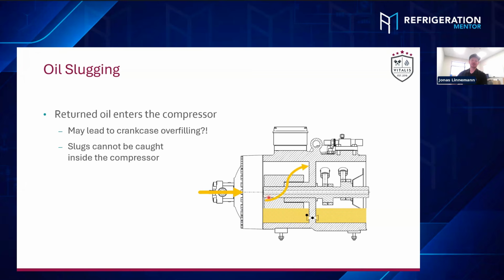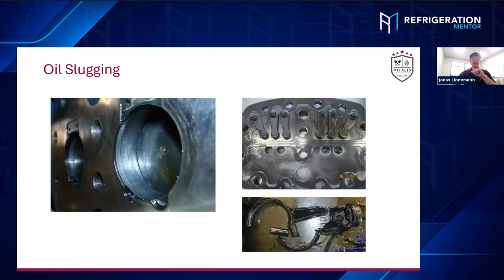And you do have a super fast spinning rotor here. The oil will not just calmly sink down, it's rotating in there. And you have the main CO₂ flow basically just pulling that oil right into the piston and just pushing it back out of the discharge line. So if you get oil slugs into the compressor, that goes immediately out of the compressor again. And that's typically looking in the field like that.